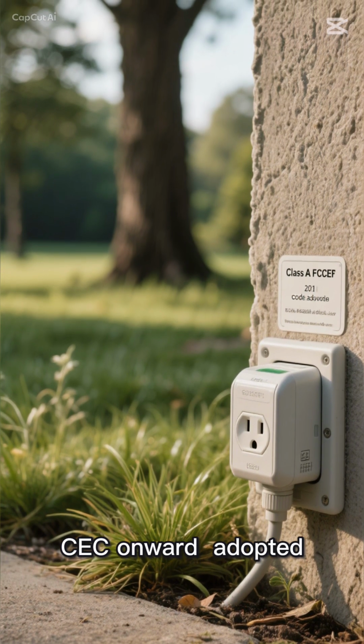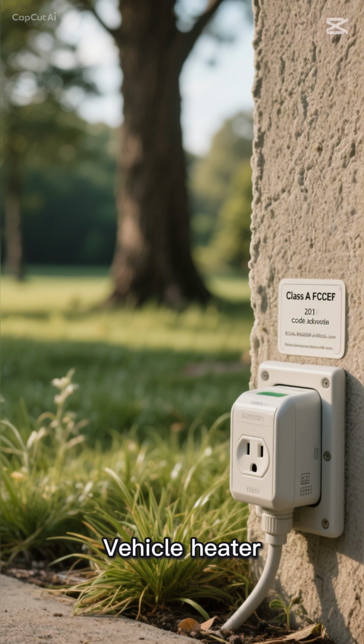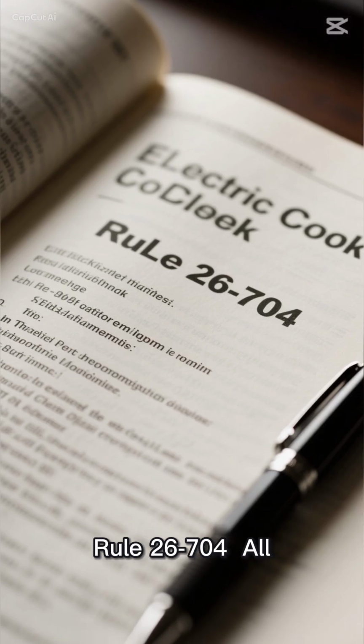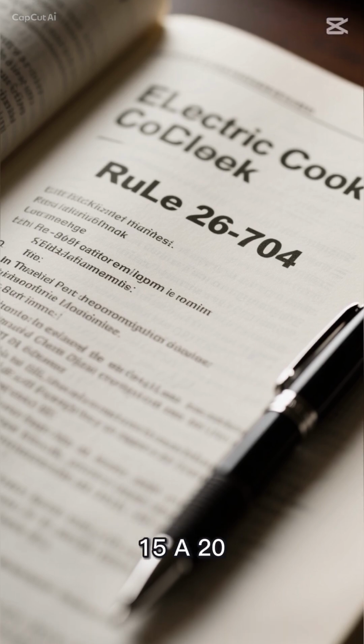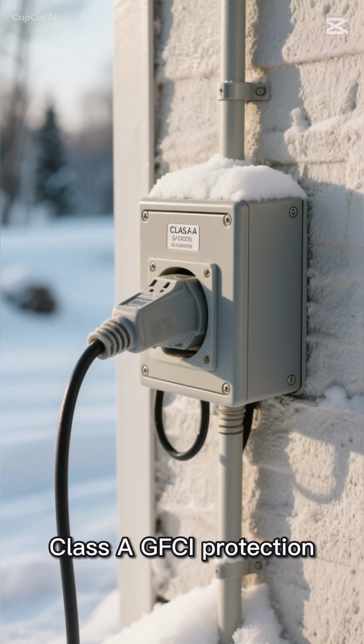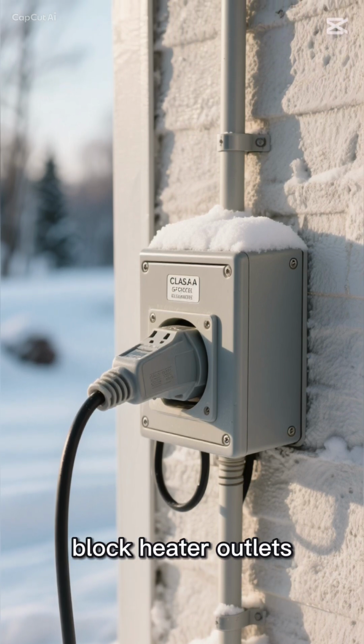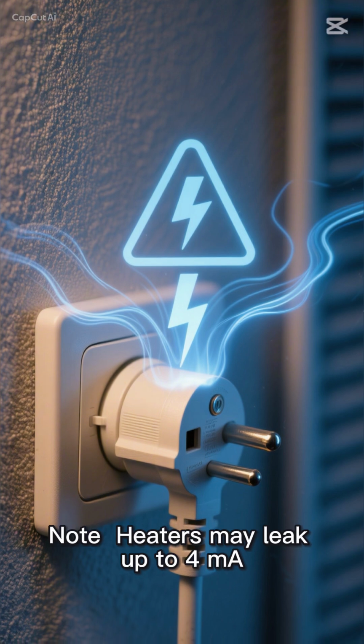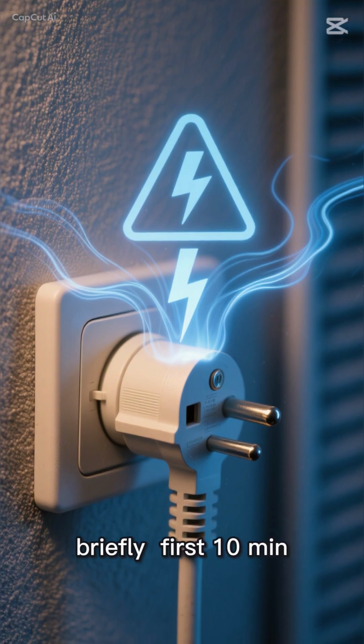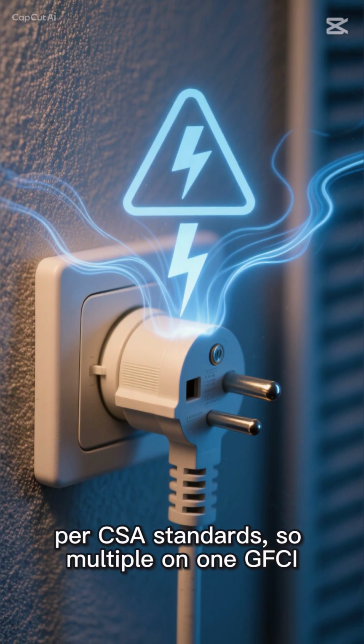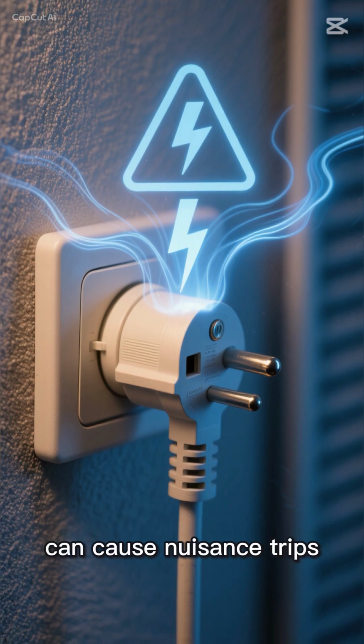GFCI protection, key update. 2021 CEC onward, adopted in Ontario. Vehicle heater receptacles are no longer exempt. Rule 26-704: all 15A-20A receptacles within 2.5 meters of finished grade require Class A GFCI protection, which includes most outdoor near-ground block heater outlets. Note: heaters may leak up to 4 mA briefly, first 10 minutes per CSA standards, so multiple on one GFCI can cause nuisance trips. Use separate circuits or careful grouping.